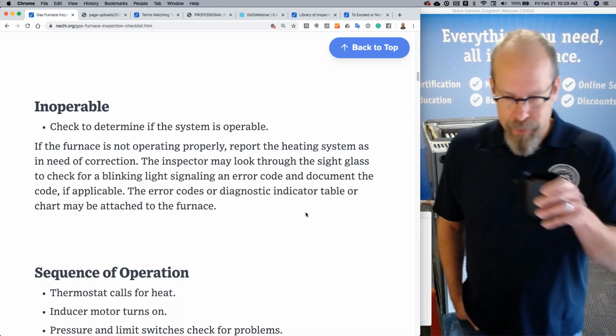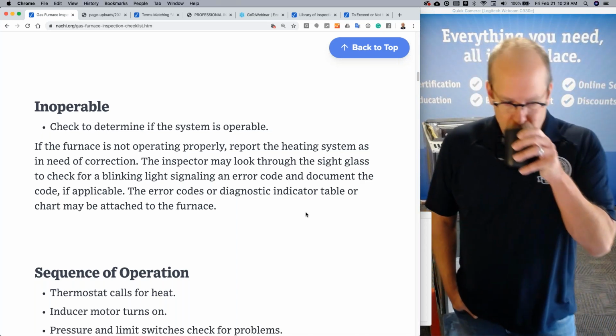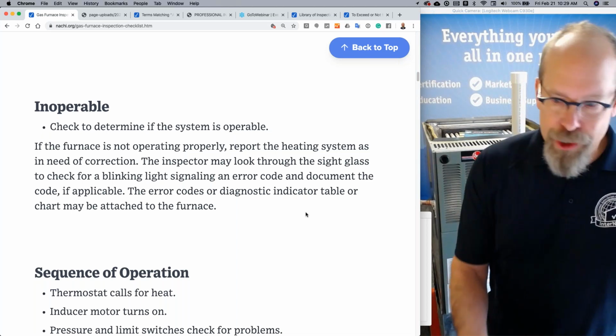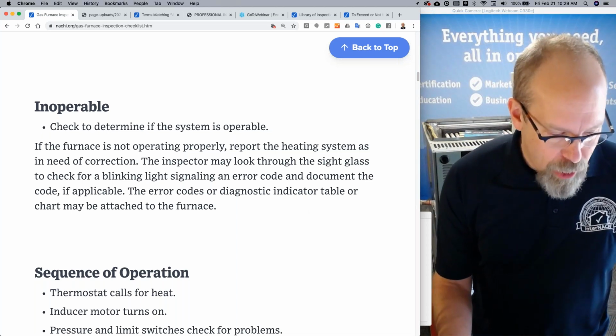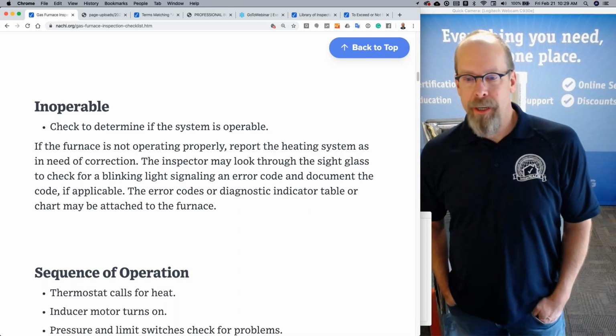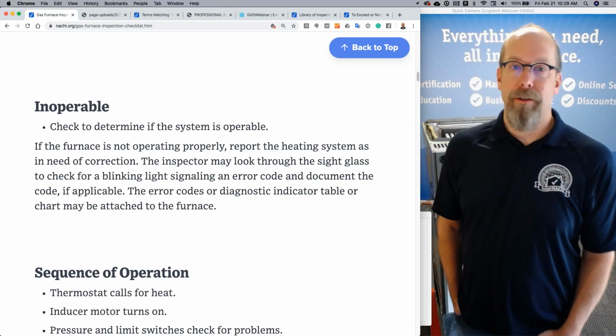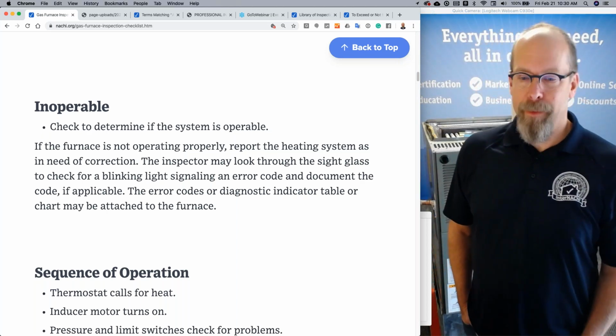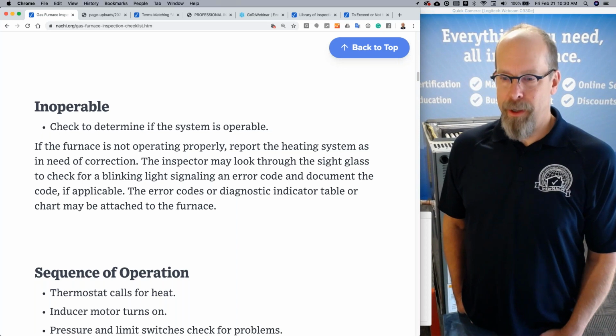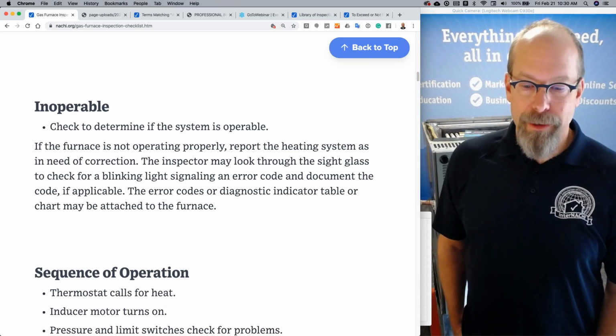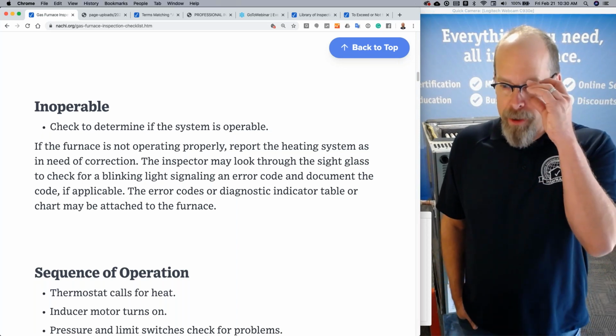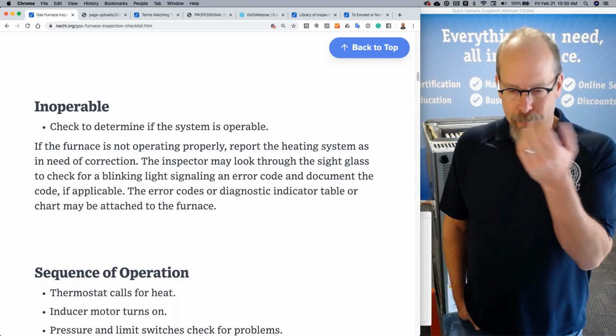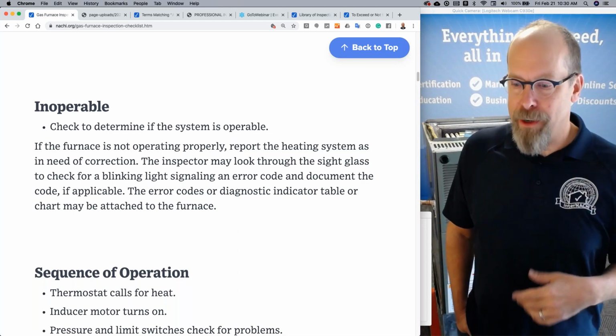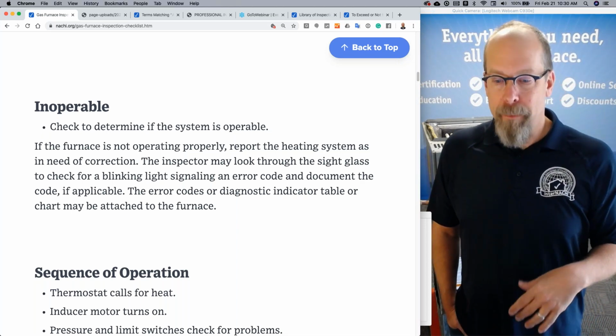Inoperable. Check to determine if the system is operable or not. If the furnace is not operating correctly, report it as in need of correction. You may look through a sight glass for a blinking light signaling an error code and document the code if applicable. Error codes or diagnostic indicator tables or a chart may be attached to the furnace.